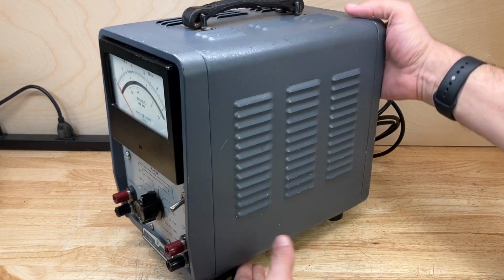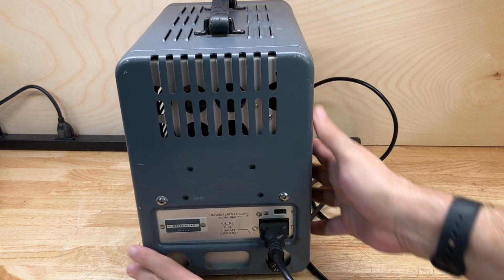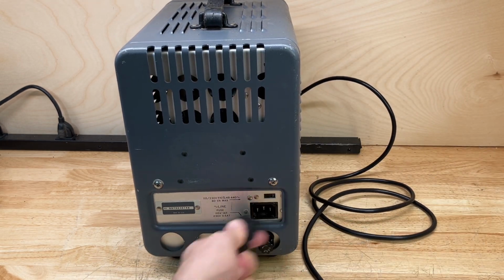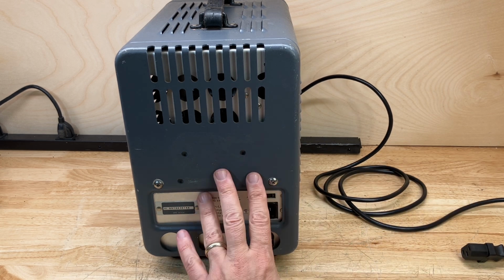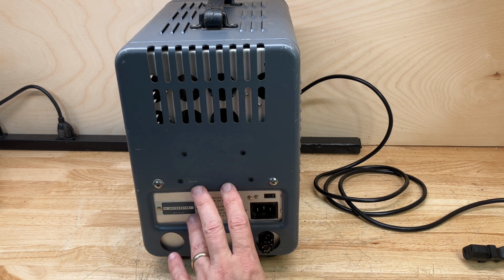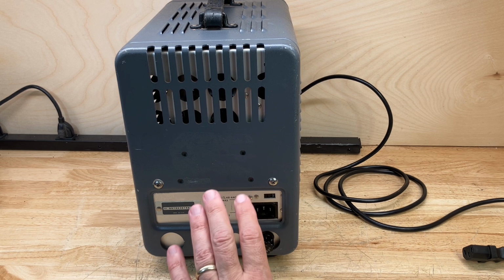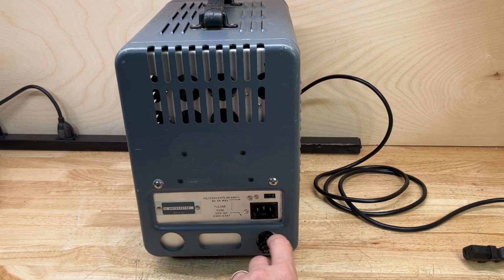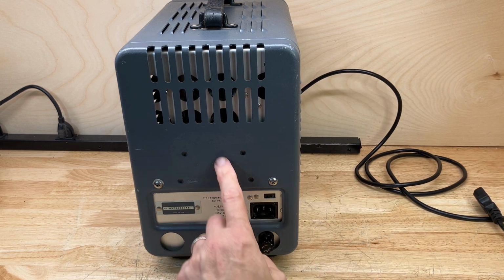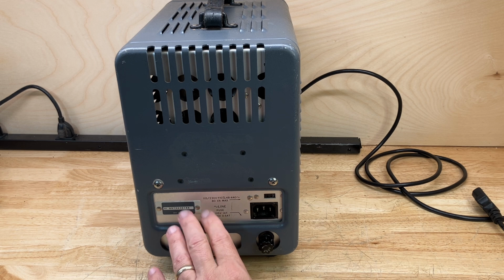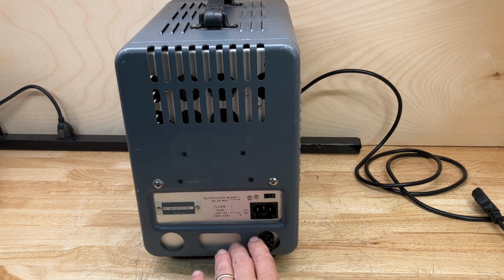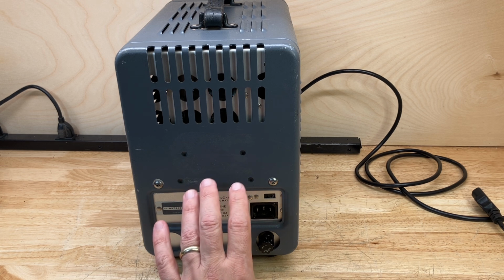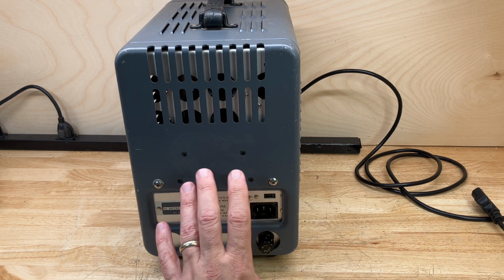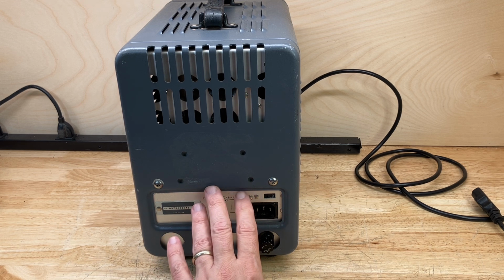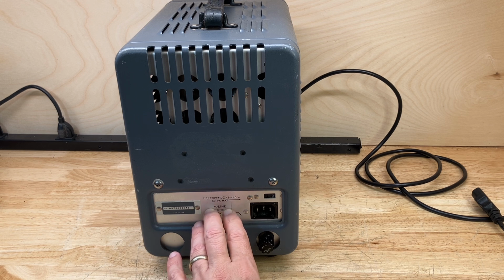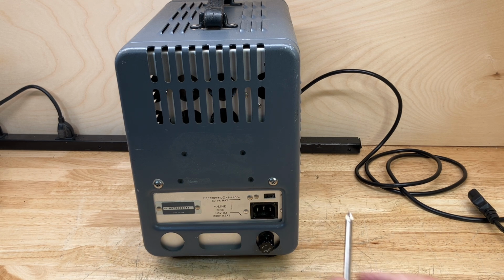Now comes the disclaimer part of the video. First, you want to unplug it. This is a tube instrument, and as such it's got high voltages, in fact lethal voltages, inside the instrument, and perhaps even when it's unplugged and turned off, because the capacitors may hold a charge, and they are very high voltages to operate those tubes. So if you don't know what you're doing, please let someone who does know what they're doing work on your vacuum tube voltmeter. You don't really want this to be the last voltmeter you ever got a chance to work on. So that's the little caveat there.